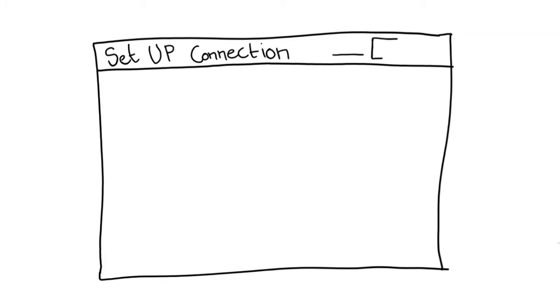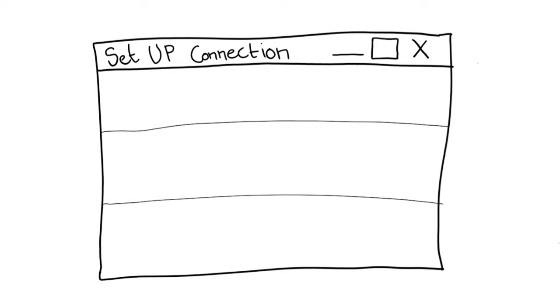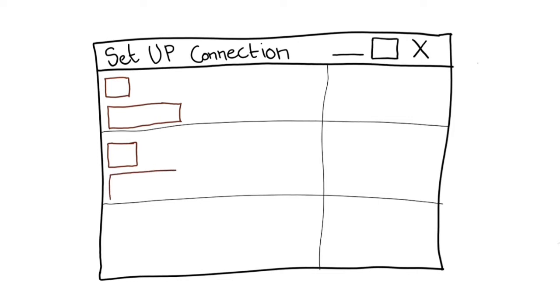For most PLCs, the service comes with the programming software. The service will usually be embedded in the software. Sometimes the service can also work on its own, but when you want to connect to the PLC, the programming software will automatically start the service for you. An example of this is Studio 5000 starting up RSLinx in Rockwell software. So when you launch the service on your engineering workstation, a configuration window will pop up.